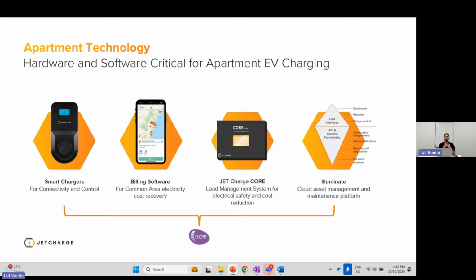The JetCharge Core load management system is built to protect against exceeding the electrical limitations of the site. It monitors how much spare electrical capacity is available in the building, then calculates how many EV chargers can be permitted to operate. It can queue chargers and rotate them in operation every hour, so that over time a fair amount of power is distributed to all connected EV chargers.